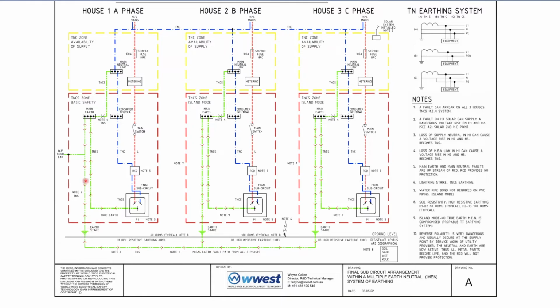But then the problems that we've just been through, like with the main earth, the main loss of neutral, reverse polarity, all the other problems, they come down here and they turn into a high resistive earthing problem, and that goes down through there. So if you've got, say, 6K here, then the operation of your RCD down here is going to be restricted. And down here, if you look at H2, we've got between H1 and H3, we've got 10Ks. So you're looking at, your resistivity is geographical. So you look at your soil types, your sand, your wet, your rock, whether it's rained in all those 4 areas, it just adds to the whole thing.